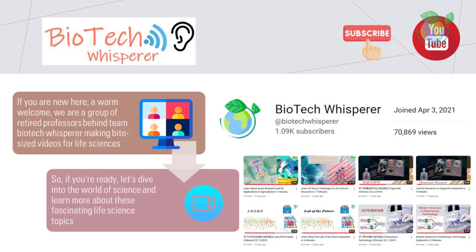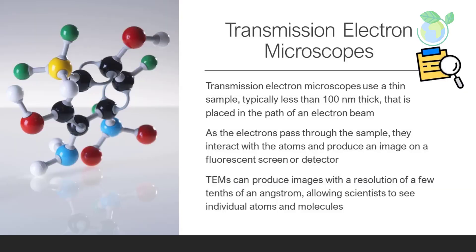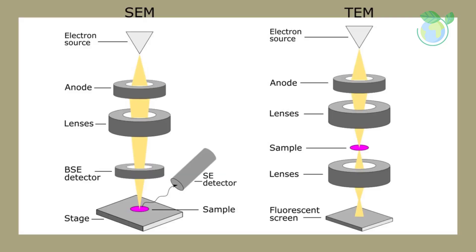Transmission electron microscopes use a thin sample, typically less than 100 nanometers thick, that is placed in the path of an electron beam. As the electrons pass through the sample, they interact with the atoms and produce an image on a fluorescent screen or detector. TEMs can produce images with a resolution of a few tenths of an angstrom, allowing scientists to see individual atoms and molecules.